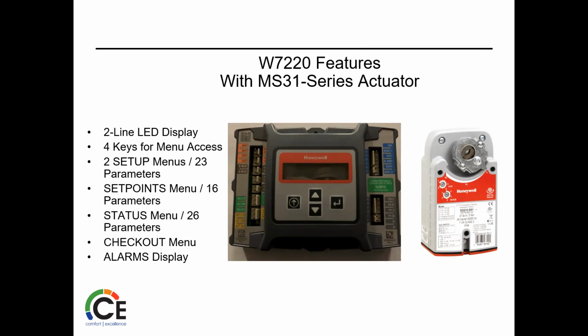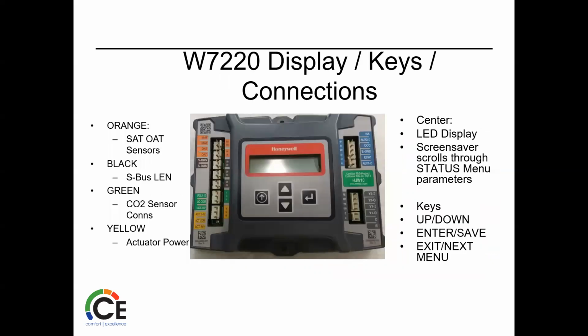So here's your communicating actuator. Again, the operation is still the same. We're talking to the control now between the actuator and the control instead of just sending voltage and hoping it does whatever it does. So 4 keys for menu access, as you can see in the middle. You've got up, down, return, access, 2 setup menus, crazy amount of parameters. So you can do a whole lot with this. Set points, 16 parameters. Status menu, there's 26 there. There's a checkout menu. There's an alarms display. So again, it's a huge upgrade from what the 7212 was.